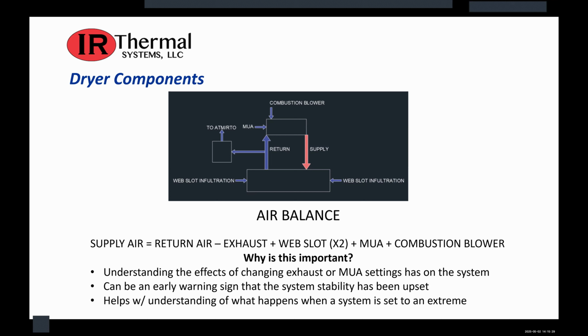So understanding the effects that changing exhaust air or makeup air has on a system is important. The supply air equals the return air minus the exhaust air plus the web slot times two plus the makeup air and the combustion blower. Understanding how all these work together can be an early warning sign that the system has been upset.